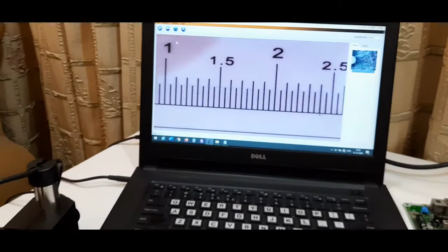See, now we will capture image. We have selected the captured image. Now we will perform the calibration. Let's select the calibration tool, then measure a known value. Here we are measuring 10 mm on the calibration scale, but actually it is showing here 6.67 mm due to the magnification. Now we will input the correct value here, which is 10 mm, and then you need to see that the adjusted magnification will appear, which is now 20x, around 20x. Then press OK tab, and the adjusted magnification will appear on the right side.